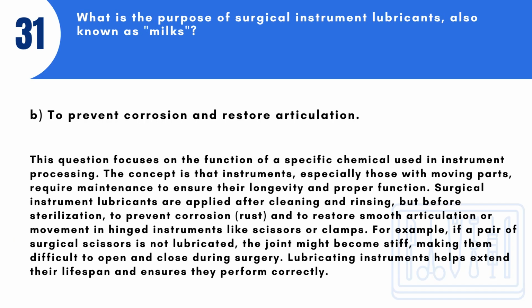Answer: B. To prevent corrosion and restore articulation. This question focuses on the function of a specific chemical used in instrument processing. The concept is that instruments, especially those with moving parts, require maintenance to ensure their longevity and proper function. Surgical instrument lubricants are applied after cleaning and rinsing, but before sterilization, to prevent corrosion, rust, and to restore smooth articulation or movement in hinged instruments like scissors or clamps.